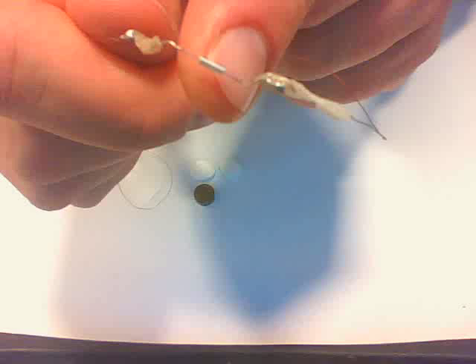So a PT100 is basically a small resistance of platinum. This may be hard to see, but it's this white piece. It has a very, very accurately determined resistance. At zero degrees Celsius it's 100, that's the basic idea.